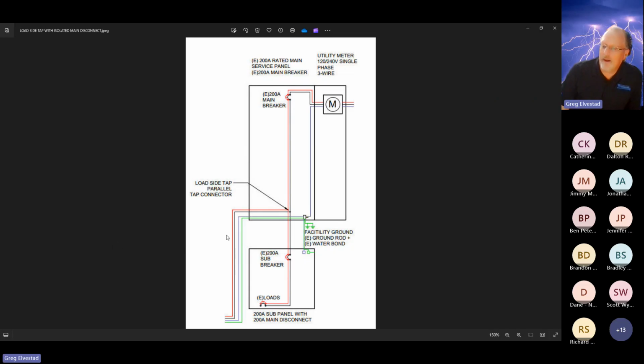So then they said, okay, we've got to protect that wire because, like I said, it's only good for 180 amps if it's 4/aught aluminum. And it's impractical to rip it out of the wall and stick in wire large enough to handle the sum total of the PV plus this. Well, what do we do? They said, well, what if we choke it? We shut it off at the rating of the wire, in this case the service wire, at 200 amps. Now, no matter what the house draws, it's only going to draw 200 amps. No matter what the PV delivers, it's going to deliver its stuff, and everything is safely protected. You've got to be worried about that.